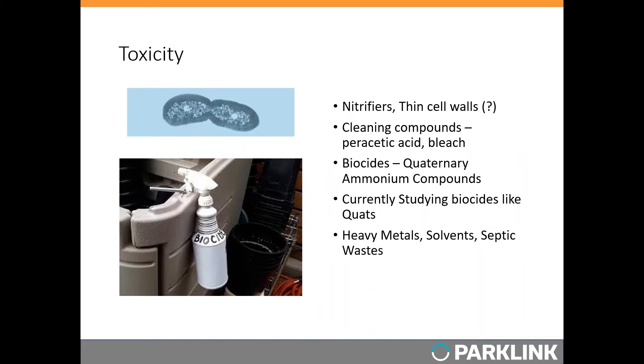Another common acute issue is biocides. Systems fed by food processors or industry commonly use sanitizers — broadly called biocides. Peracetic acid is one example; quaternary amines are another. These biocides are designed to kill bacteria indiscriminately. When sprayed on surfaces they wash down into floor drains and eventually into the wastewater plant. With a lot of dilution from other influent the diluted biocides may not be a problem, but a large dump or a processor using biocides that make up a large percentage of your influent can quickly become a problem.